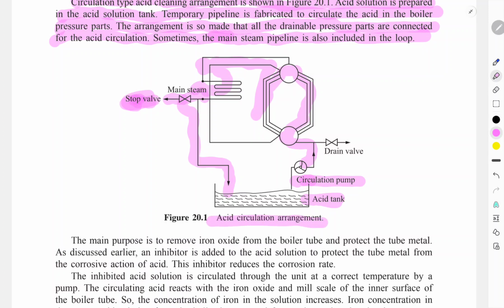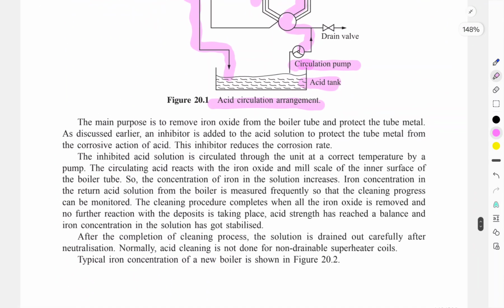So the acid circulation arrangement is very important to clean the boiler before commissioning. The main purpose is removing iron oxide from the boiler and protecting the tube metal. As discussed earlier, an inhibitor is added to the acid solution to protect the tube material from the erosive action of the acid. The inhibitor reduces the corrosion rate. The solution is circulated through the boiler at the correct temperature via the pump. The acid reacts with the iron oxide and mill scale on the surface of the boiler tube.